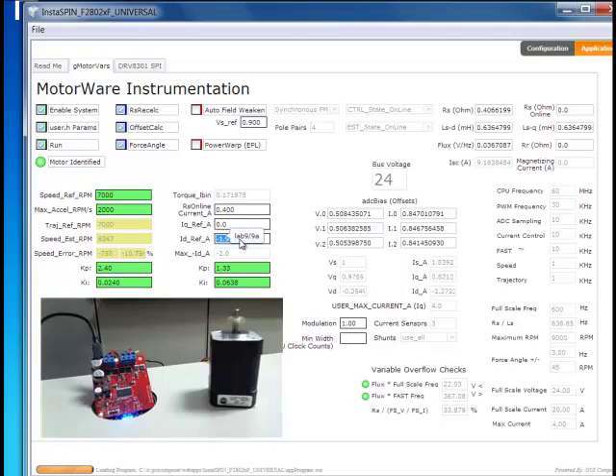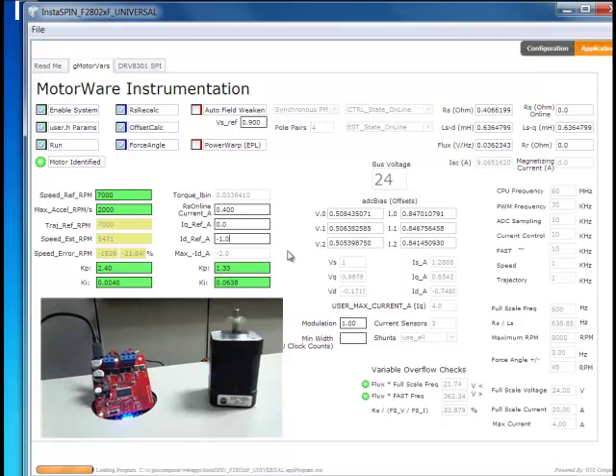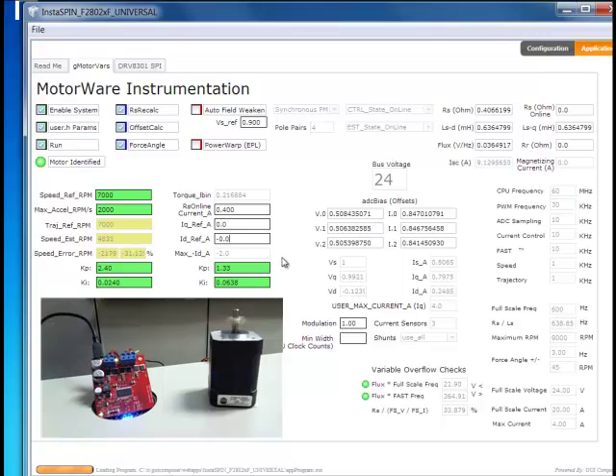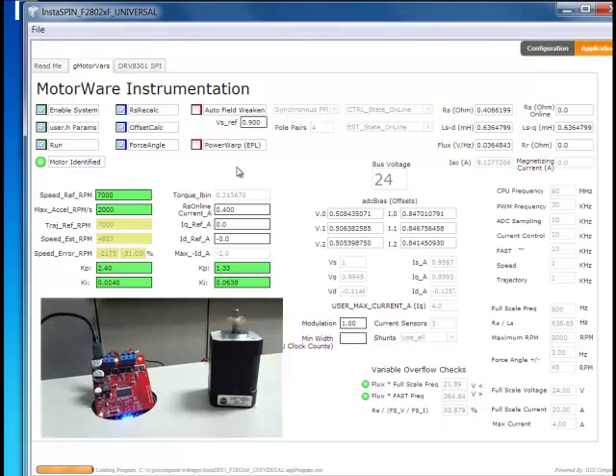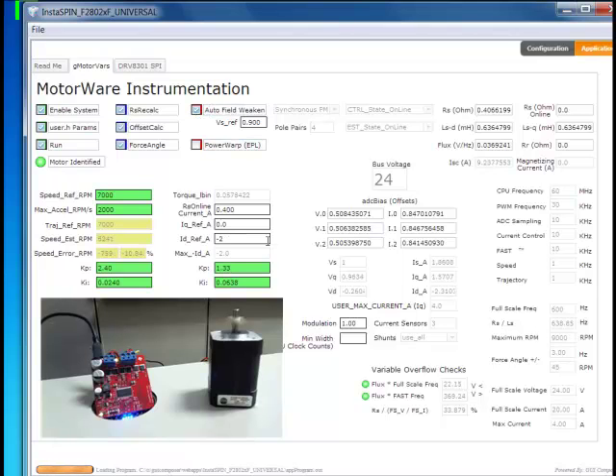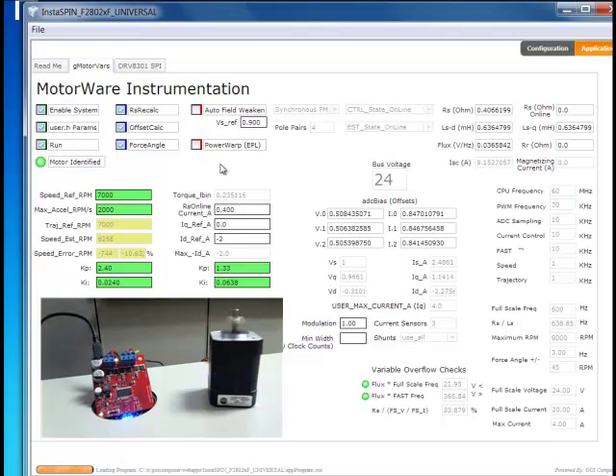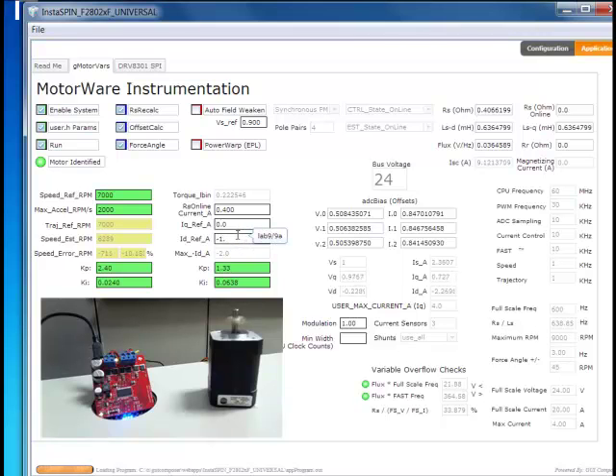Now let's see what the auto field weakening does. For this, let's slowly change this current back towards zero. You want to do this in a controlled manner. You don't want to just switch it off fully or you can have some regenerative effects. So slowly reduce the current back to zero. Now we can try the auto field weakening. The auto field weakening is going to add this ID as necessary up until the limit. If we turn this on, you can see the ID increases and it clamps all the way to 2 because it's still trying to reach the 7,000 RPMs and it's not able to. When you remove the auto field weakening, you'll notice that the ID reference remains. You also need to take this out manually and again, do it in a controlled fashion.